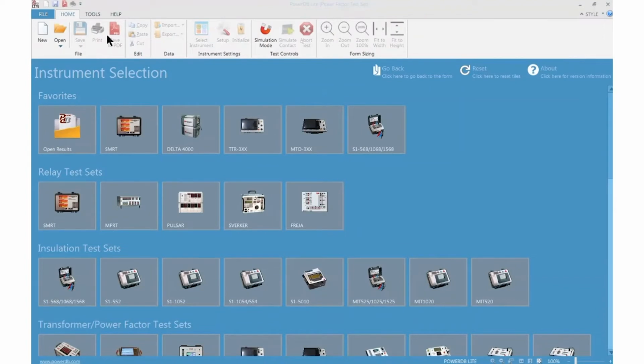One additional thing, once you have completed a test and you have the report ready, you can generate a PDF version of that result with this button, so you don't need any additional PDF printer or generator installed. Also, you have the option to import data, specifically from an old software for the BITE, the battery impedance testers. You can import data from ProActive databases, and the export function will work. When you have a result, you can export to a CSV file, or specifically for the power factor test, you can export the result to a DTA 5 or DTA 6.